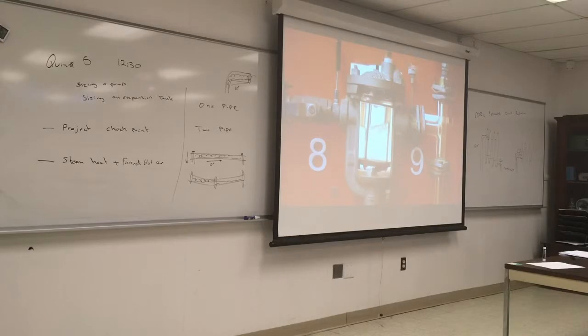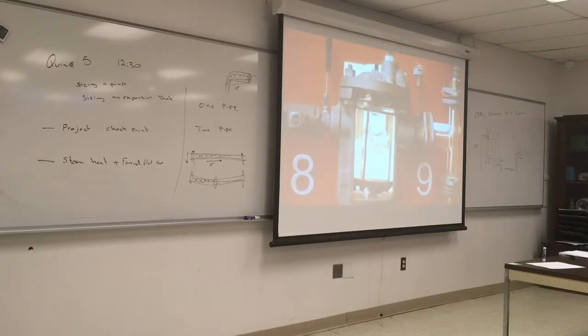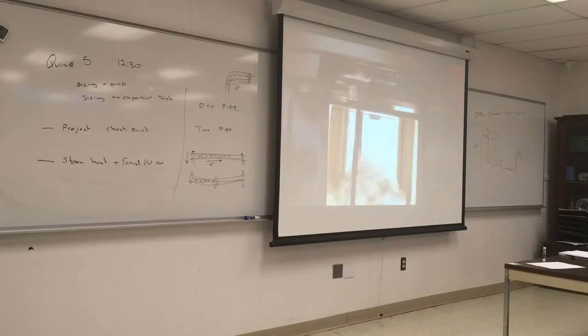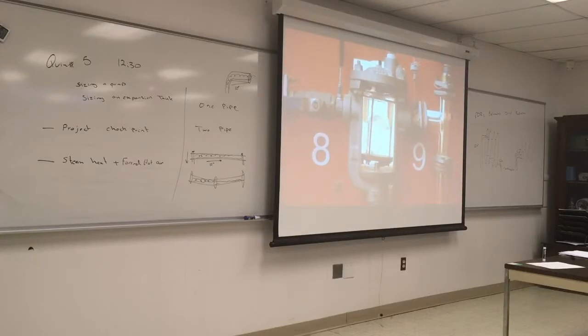Radiation causes the steam inside the bucket to cool and condense. If the condensed steam is replaced by more steam, the bucket remains buoyant and the valve closed. However, when enough steam has been condensed by radiation and is displaced by entering condensate so that only one-third of the bucket volume contains steam, the bucket loses buoyancy. As more steam condenses, the bucket becomes heavy enough to pull the valve off its seat.